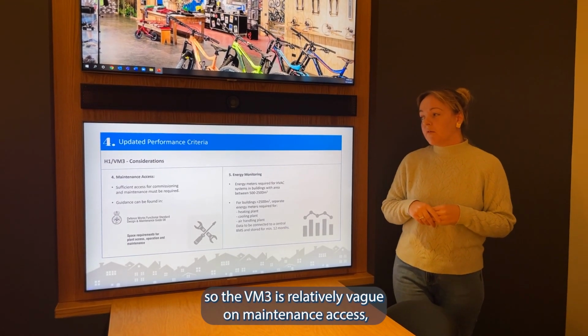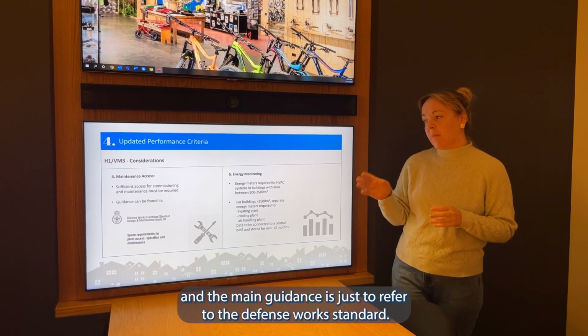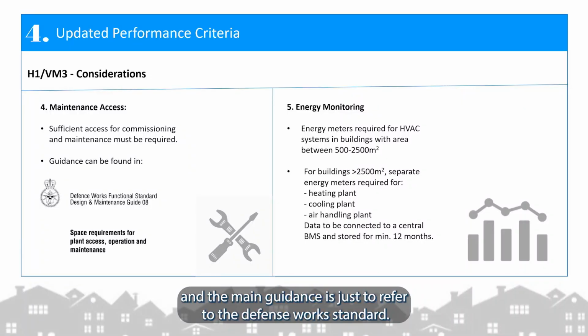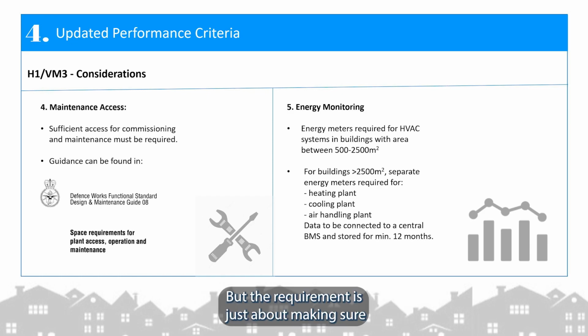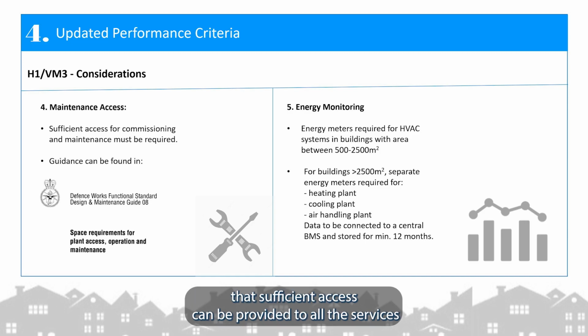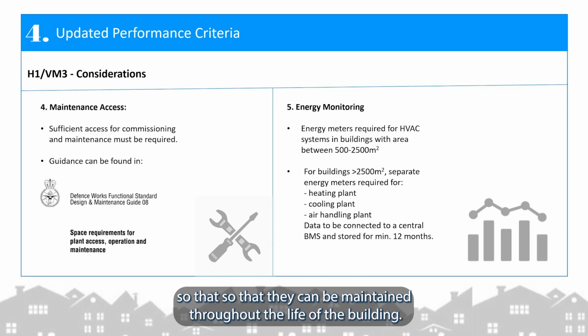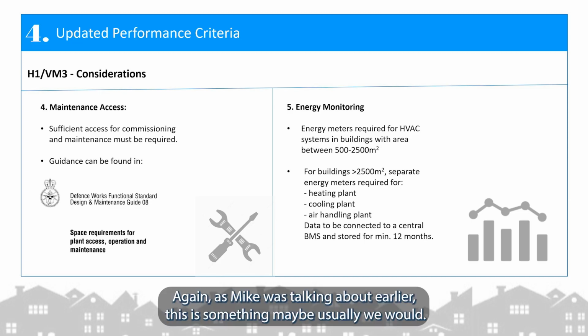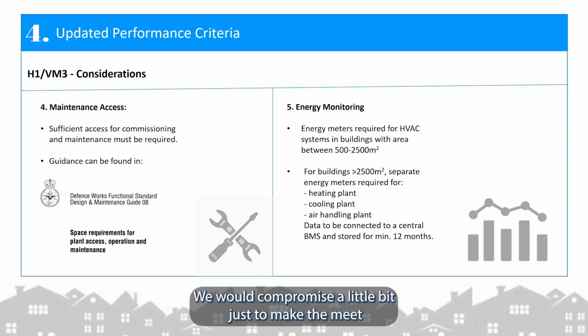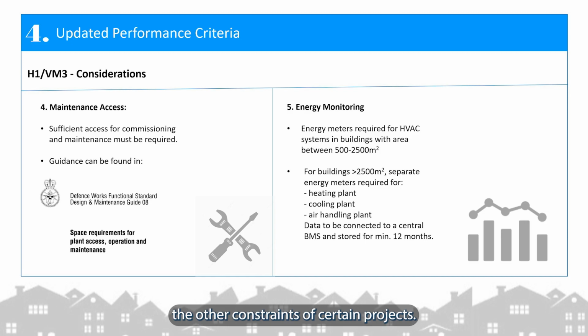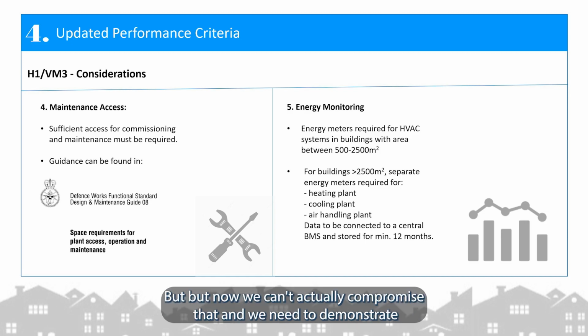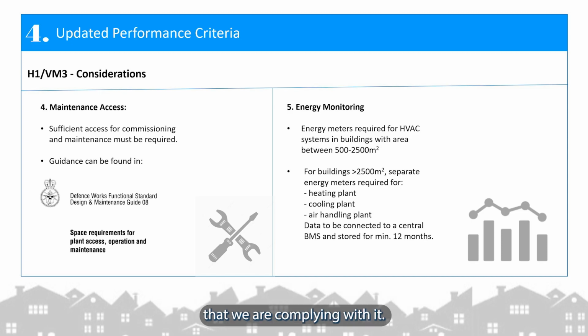Next, there's maintenance access. The VM3 is relatively vague on maintenance access, and the main guidance is just to refer to this Defence Works standard, but the requirement is just about making sure that sufficient access can be provided to all the services so that they can be maintained throughout the life of the building. Again, as Mike was talking about earlier, this is something we usually would compromise a little bit just to meet the other constraints of certain projects, but now we can't compromise that, and we need to demonstrate that we are complying with that.